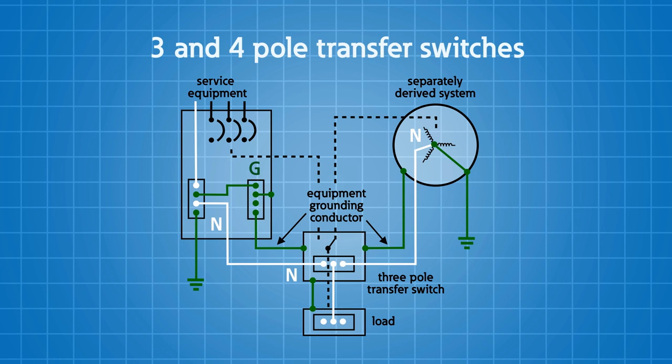And to get that done, I need to switch the neutral in the transfer switch. So that means I would need to have, say for example, a four-pole transfer switch. If I do that, I put a four-pole transfer switch in, I switch the neutral, and everything is fine.